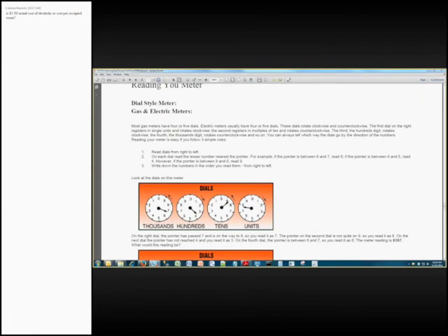I've seen electric meters with a multiplier of 120 or 200, even 300. So what you do is you take the value on the display, multiply it by your meter multiplier, and then that's your final value that you would enter into the system. So for example, if you have an electric meter that says 50 kilowatt hours, and it has a meter multiplier of 100, the value entered into the app would be 5,000 kilowatt hours.